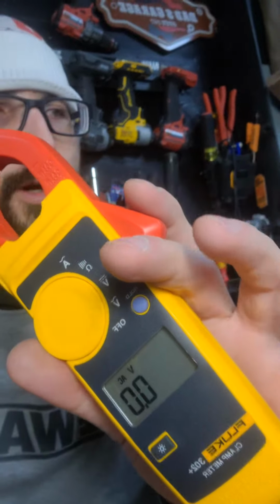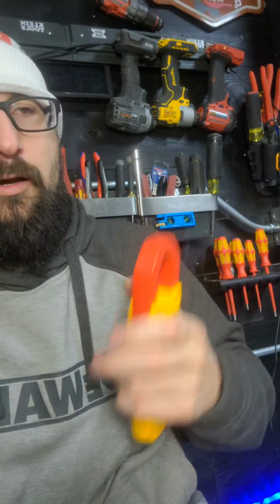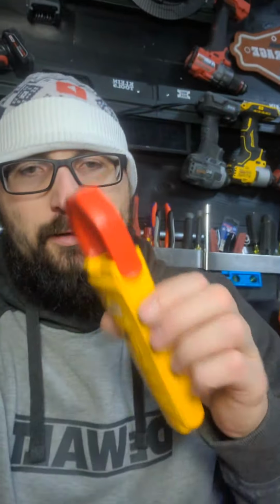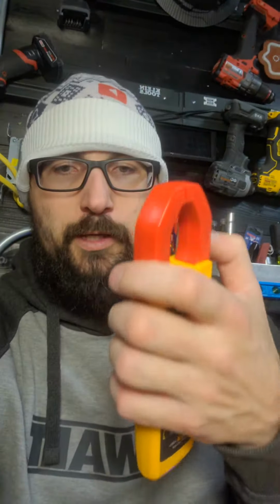Yes man, the Fluke 376 is a great meter, it's also an expensive meter, but it's a great meter. This is the question: if you were to troubleshoot and you're running back and forth between all the outlets in the room, pulling them out, checking voltage—because when you're looking for a loose connection, you typically leave the power on, that way you know when you found the problem. So you're not going to go to the panel, turn off the circuit, and pull every plug out of the wall. You're going to leave the power on, pull the plug out, and see if you get power as you're working. So the question is, are you going to take your $500 multimeter to every outlet, set it on the floor that many times, and test with, you know, no lead grabber, all that stuff?